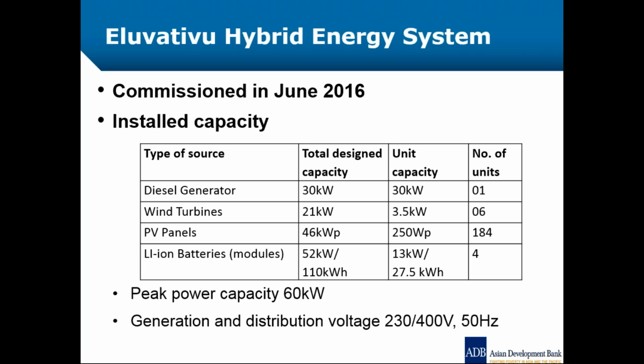The project was initiated around 2014. Contracts were awarded in 2015, and within just over a year the project was commissioned, in June 2016. Installed capacity: diesel generator 30 kilowatts, wind turbines—6 turbines at 3.5 kilowatts each—PV panels 46 kilowatt peak, and a battery of 52 kilowatts at 110 kilowatt hours.